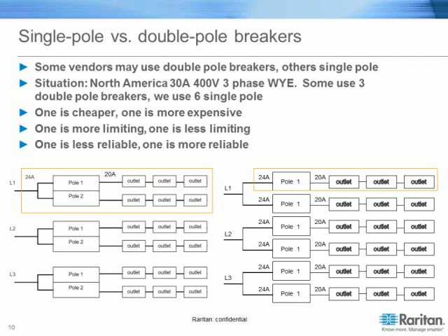It's a joke out there - people see open plugs in a data center and think, I must have power, the plugs are open. So by having just a single double pole breaker for these 6 outlets, we are almost inviting ourselves to trip this breaker.